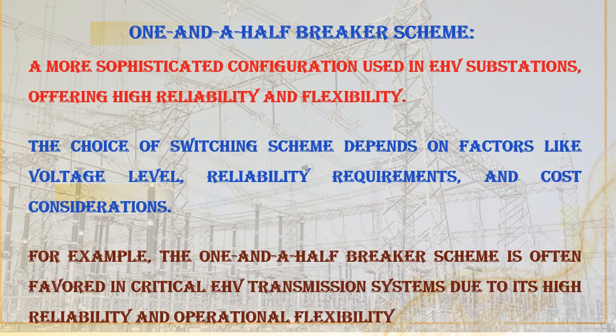It is a more sophisticated configuration used in EHV substations, offering high reliability and flexibility. The choice of switching scheme depends on factors like voltage level, reliability requirements, and cost consideration.